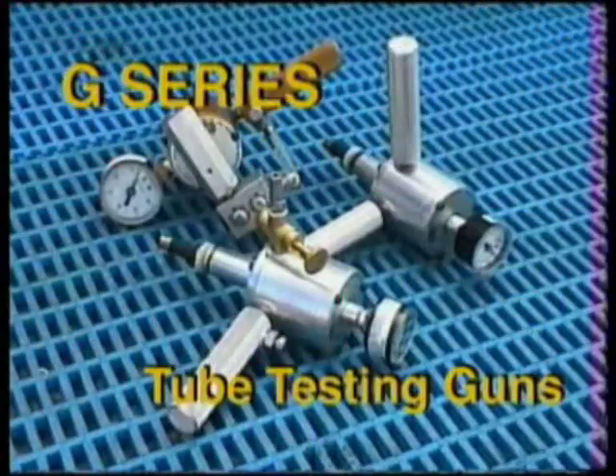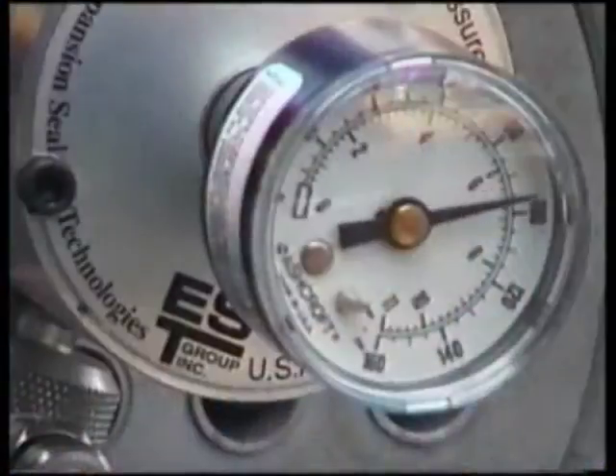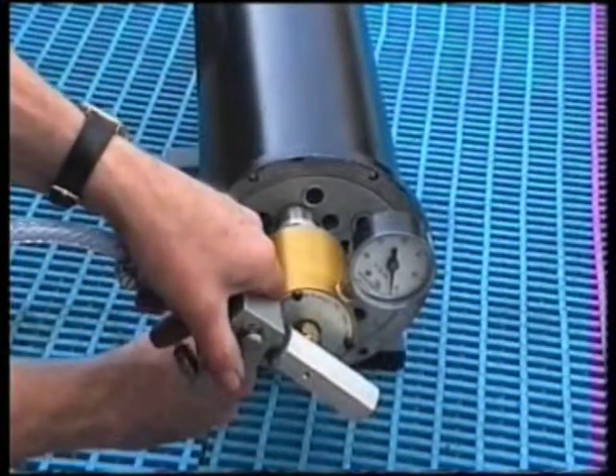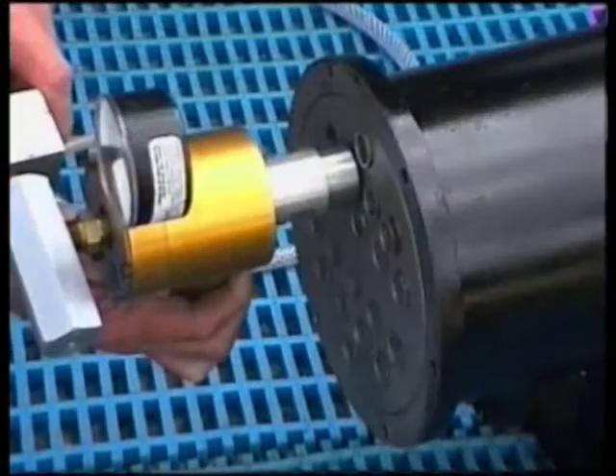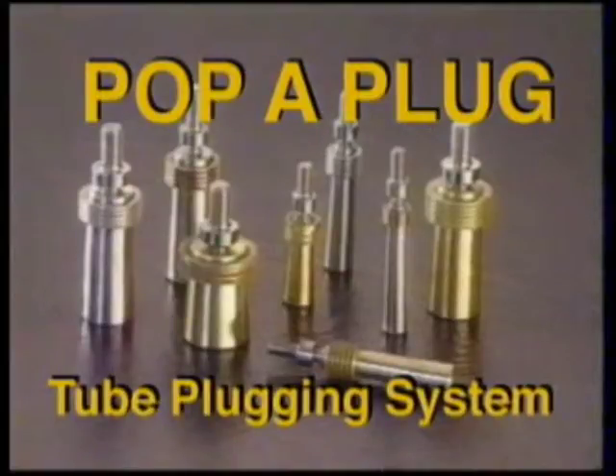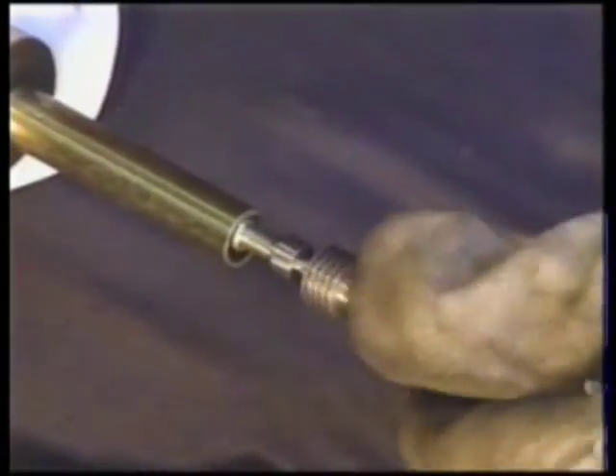G-series tube testing guns provide high-performance, high-volume production testing. The G-150 tube testing gun — the fast, effective way to test for tube leaks. Whether straight or U-tube, the G-150 can detect pinhole tube leaks at a rate of up to 10 tubes per minute. The G-650 vacuum joint testing gun generates a vacuum around the tube-to-tube sheet joint to pinpoint leaking connections. The Pop A Plug tube plugging system — with simple hydraulic installation, the Pop A Plug system maintains guaranteed leak-tight seals under extreme thermal and pressure cycling.